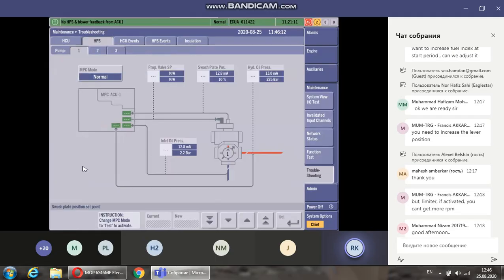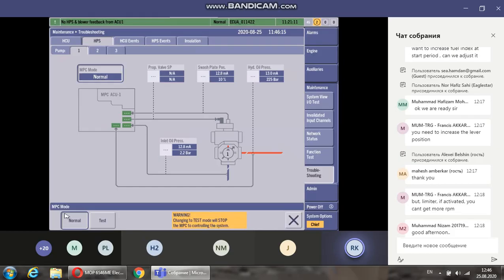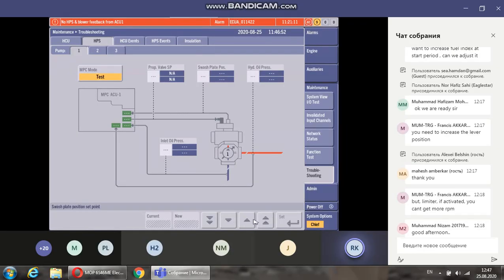Hydraulic power supply, here we can also take the MPC into test mode. If I just do this now so we can see what's going on, we can also adjust the position of our swash plate from this screen, giving us a good swing through check of our swash plate position using the proportional valve for the movement.